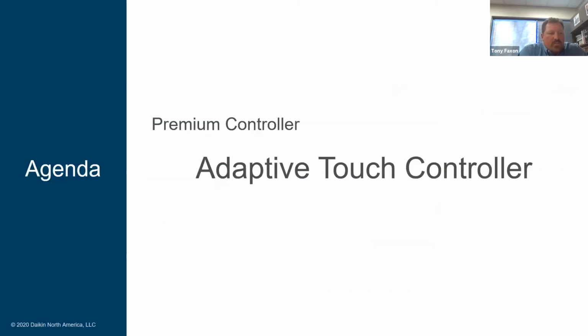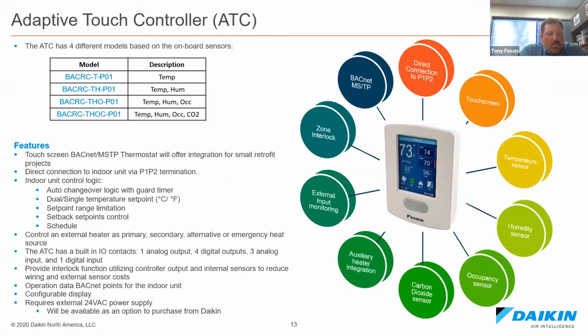The next innovation I wish to discuss is the Adaptive Touch Controller, or the ATC as it's commonly called. The ATC is currently estimated to come to the US market in first quarter 2021. It's a premium controller that would typically be used in commercial applications where more features are desired. There are going to be 4 models of this controller, which will determine what sensors the end user wants. Temperature, humidity, occupancy, and CO2 sensors are all available. It has a clean looking touchscreen with scheduling, single and dual set points, auto changeover with a guard timer, all the normal controls you would expect.